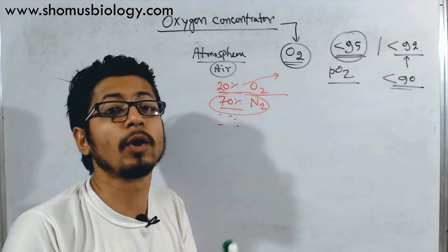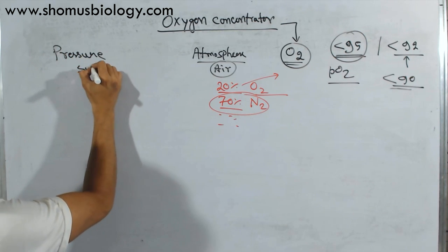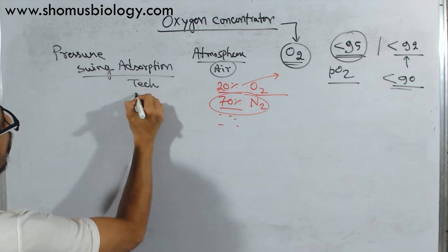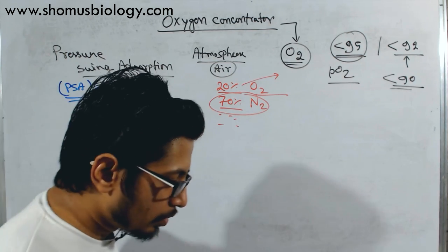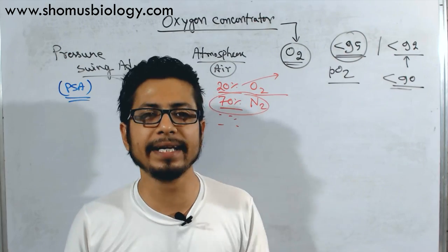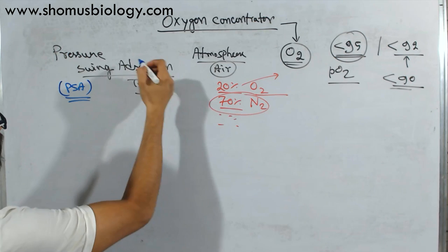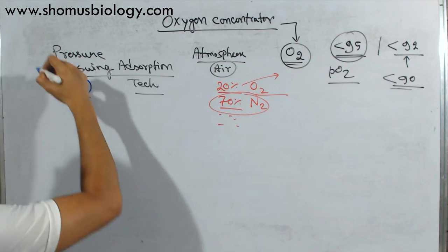So that's what we need to do — we need to separate oxygen from nitrogen. For that reason we have what is known as Pressure Swing Adsorption — PSA technology. This is the technology we use to separate oxygen from the nitrogen in the air. Using this machine at home, we can separate nitrogen from air and bring out pure oxygen. Another technology is the molecular sieve, but we will focus mostly on the PSA model.